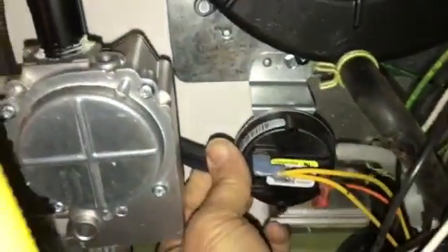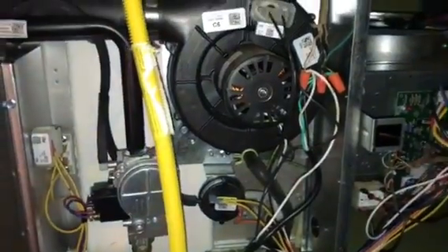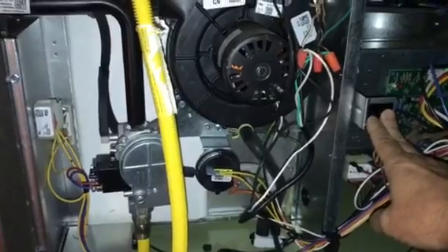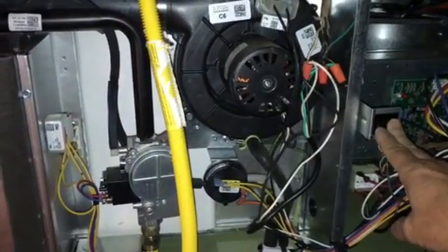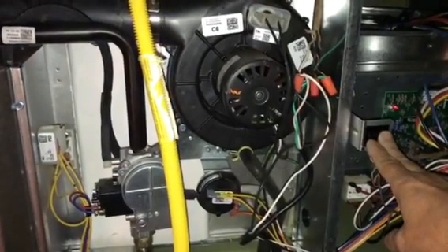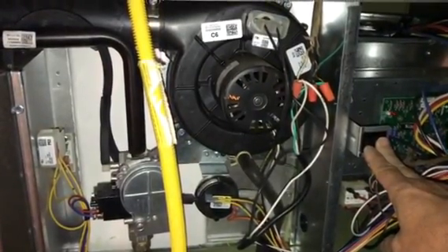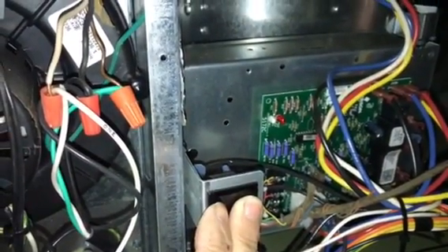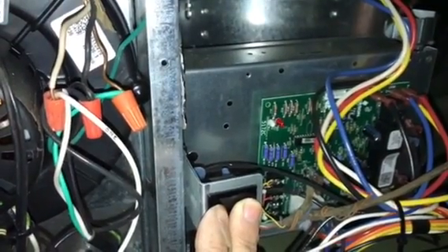Doesn't have any water improperly in it. What worries me is if we pull that tube off like that and draw and blow on it and it goes back to working right, is it going to do it again in the middle of the night tonight? So I will go look through the truck and see if I have that pressure switch. You know, getting the normal blinks. At least we will. And it says it's stuck open again.